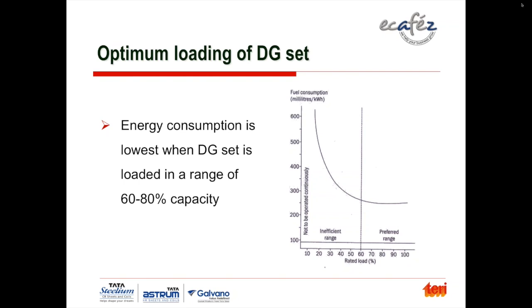The preferred range, which is indicated, is to load a DG set 60% to 100%. So the selection of the right size of the DG set becomes very important. Like for air compressors, this is again very important. One should not have a larger size thinking of expansion for the future.